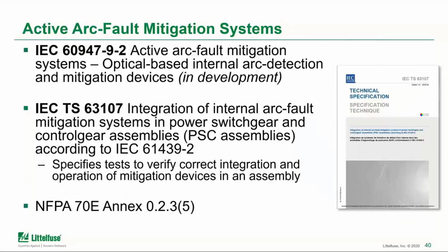So one comment that is often mentioned for the arc flash relays or arc fault mitigation systems, as it's mentioned in the code, is that it can be difficult to align with some of the switchgear testing and to verify that it's correctly installed. And there are a few fairly recent standards on the market that are working to address that. So I think it's worthy to mention as an update.